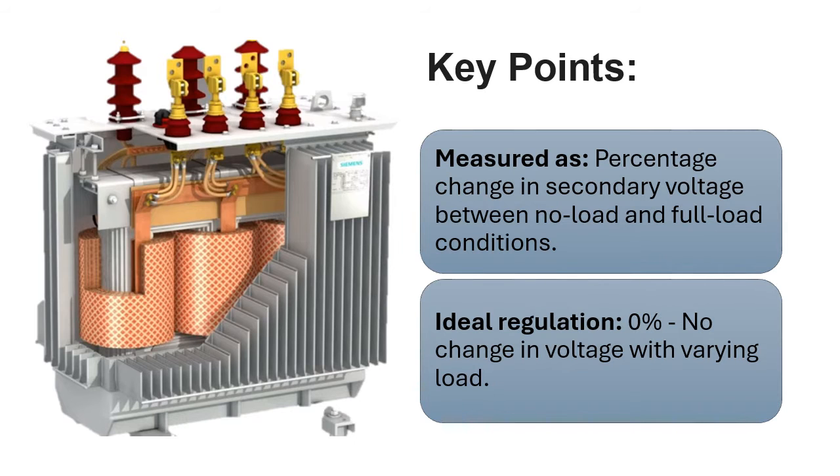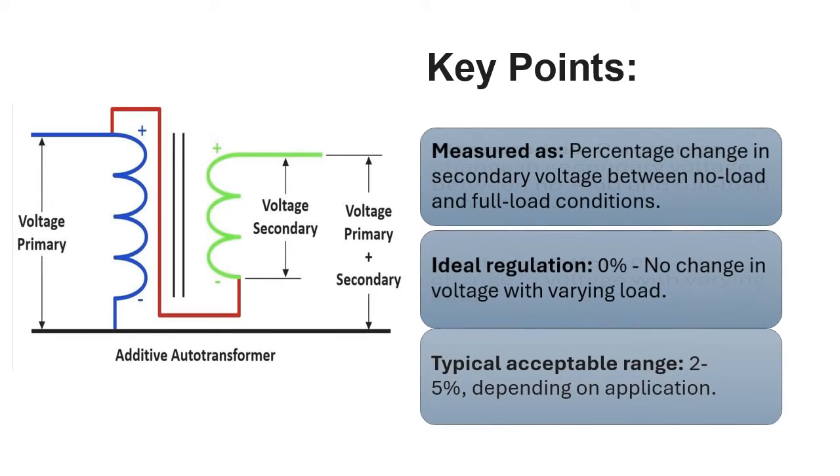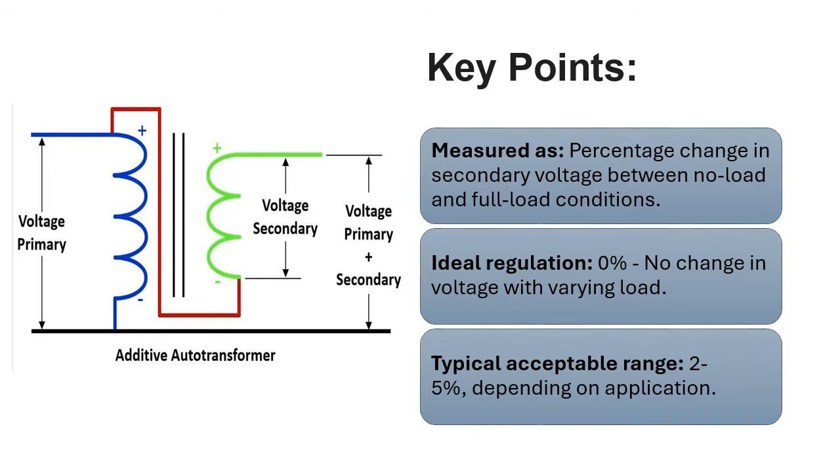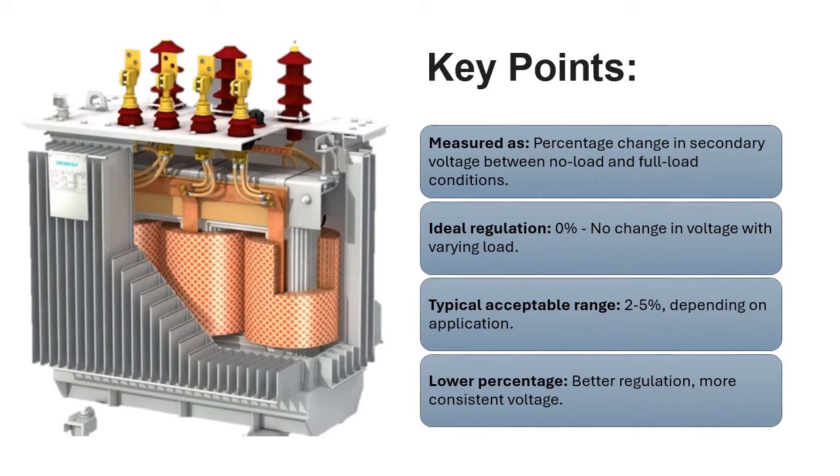Typical acceptable range is 2-5% depending on application. Lower percentage means better regulation and more consistent voltage. Factors affecting regulation include leakage reactance, copper losses, core losses, and load power factor.